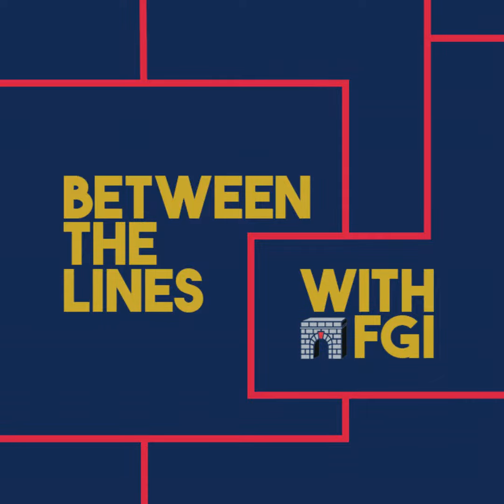So there are other things associated with that quench piping, that quench vent, that are requirements in the guidelines. I imagine as you're describing this force of energy and gas moving through there, there are all sorts of hazards associated with that. It typically discharges on the roof, right? Most facilities, yes. Have you seen mistakes of the vent in the guidelines? It's called the cryogen venting point. But have you seen designs where that has been placed in a less than optimal location?